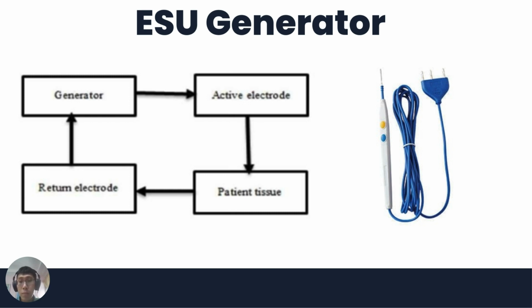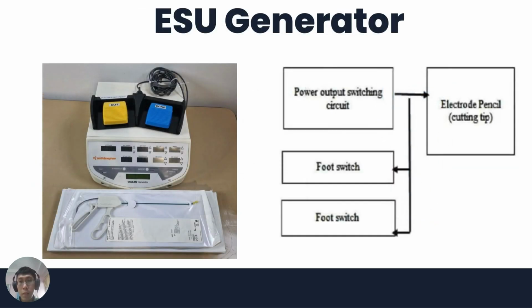The return electrode is present in the monopolar type. The return electrode provides the return path to the electrosurgical unit. Tenth, hand tool. The surgical pencil has two modes, cutting and coagulation. A high frequency voltage and power are required for cutting. The power level varies from 100 to 750 watts, depending on the type of application. Eleventh, foot switch.